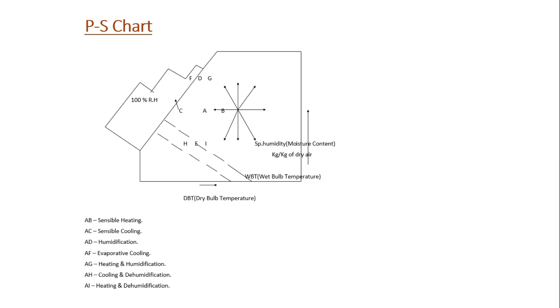Various processes normally include sensible heating, sensible cooling, humidification, evaporative cooling, heating and humidification, cooling and dehumidification. You have to draw your process on the psychrometric chart from the outside ambient condition to the indoor condition, and accordingly select your equipment. I know everybody is familiar with the basic mechanism of the psychrometric chart since you all are air conditioning engineers who qualified with a basic air conditioning degree.